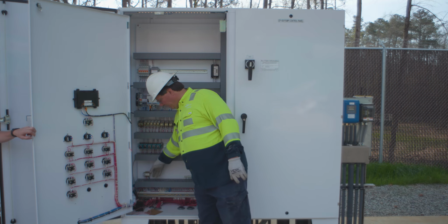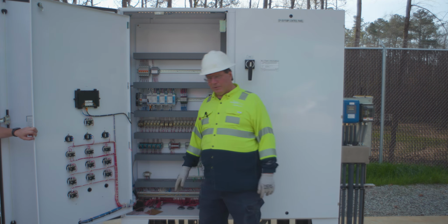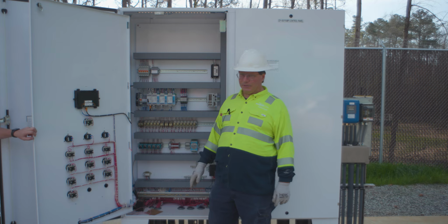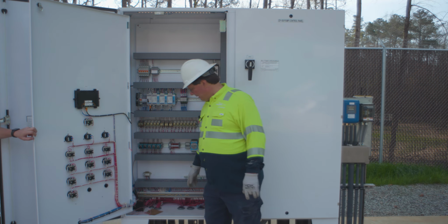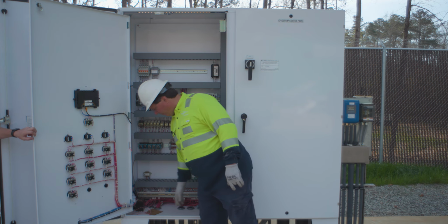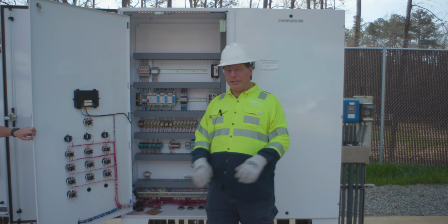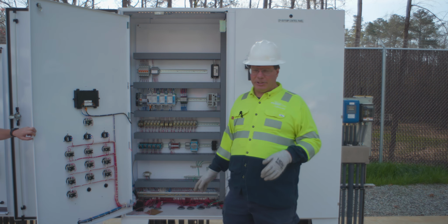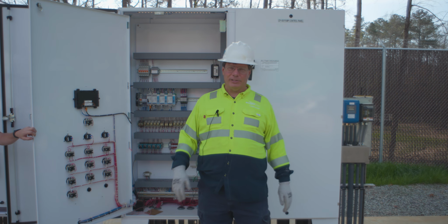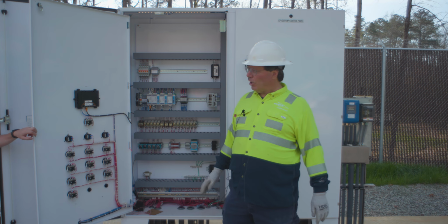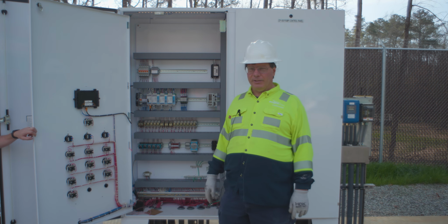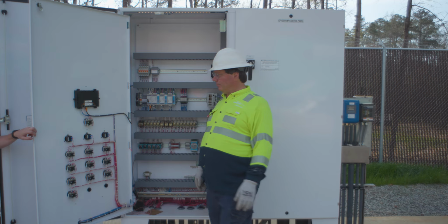This is the power supply for the mission unit. It's 12 volt DC, class 2 transformer, 20 volt amp. And this is a little battery for the mission unit, so if everything else loses power, the mission unit can still monitor that high level float and tell them if there's a high level and call them on a separate system altogether as a backup.